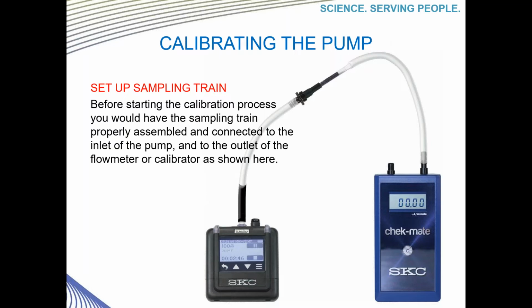Now that we have set the flow rate, I want to go through a basic single point calibration so that you can see how nice it is to be able to perform the calibration just using the touch screen. At this point, if you hadn't already, you would need to go ahead and set up the sampling train to perform your sample just as you would in the field. Then attach it to the Flowmeter or Calibrator. In this illustration, we have the Pocket Pump Touch connected to a single non-adjustable tube holder, which I have removed the tube cover, then a sorbent tube, and then to the SKC low flow Checkmate calibrator.